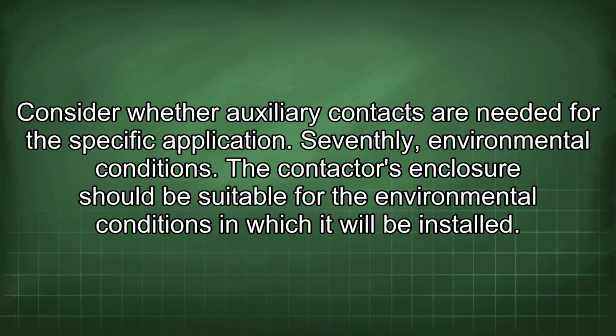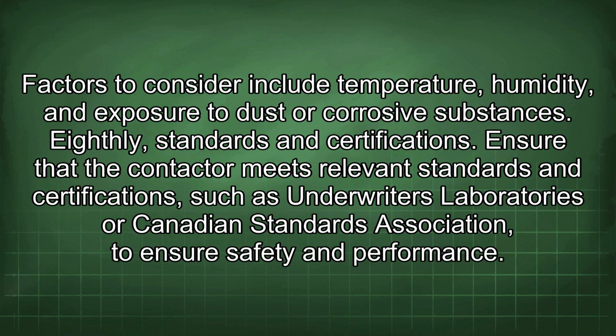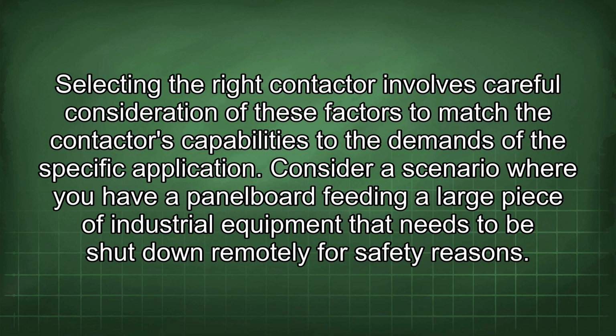Seventhly, environmental conditions. The contactor's enclosure should be suitable for the environmental conditions in which it will be installed. Factors to consider include temperature, humidity, and exposure to dust or corrosive substances. Eighthly, standards and certifications. Ensure that the contactor meets relevant standards and certifications, such as Underwriters Laboratories or Canadian Standards Association, to ensure safety and performance.